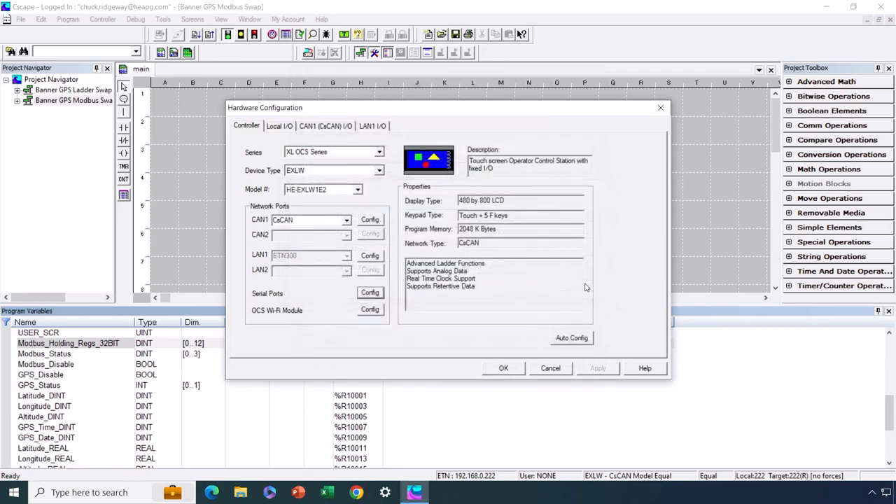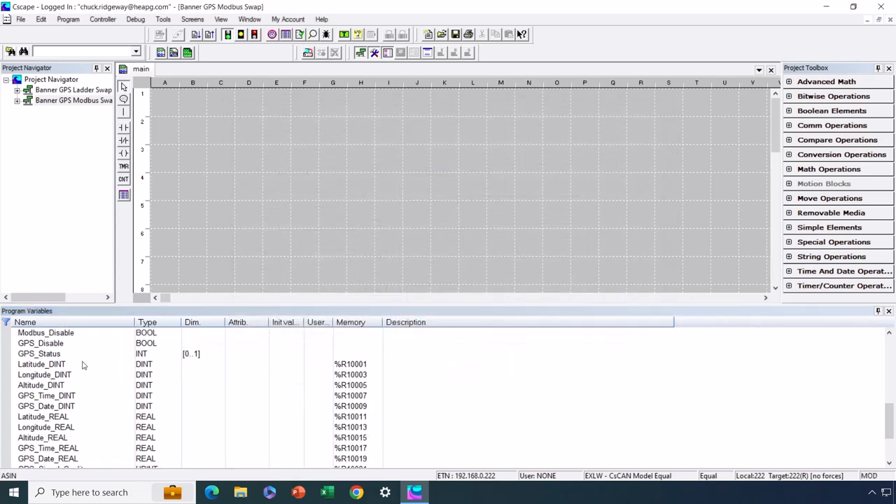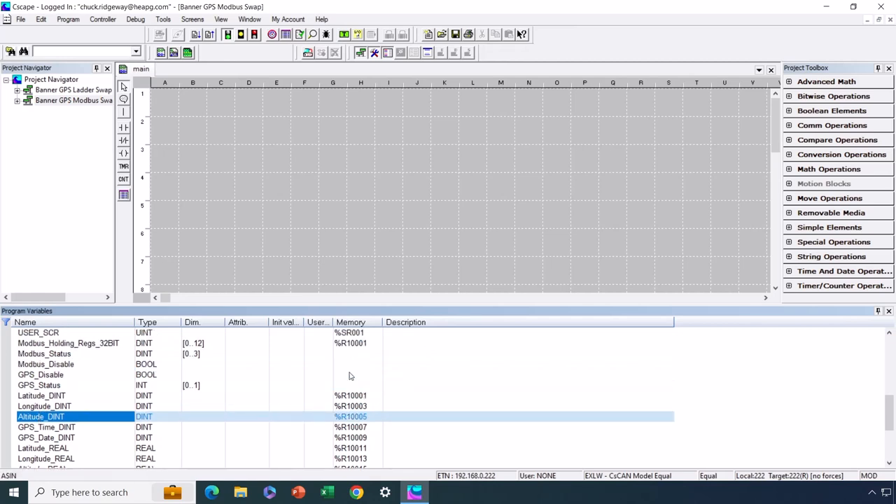Most of you would probably say you prefer the Modbus swap approach because there are fewer variables to create. The last step is still to create the final variables for latitude, longitude, altitude, etc. and map them to the appropriate location in the Modbus array so the data magically shows up in the right variables. The screens are identical to those created for the ladder swap approach — the same screens with the same information.